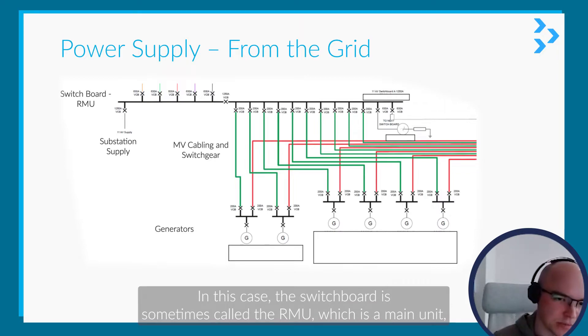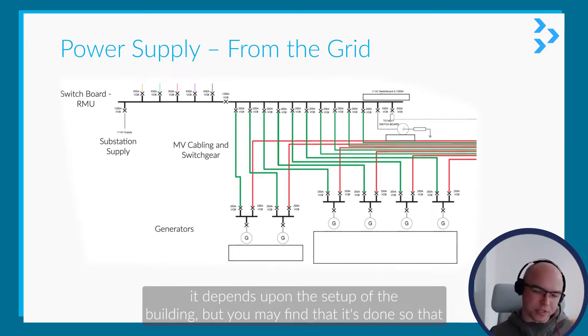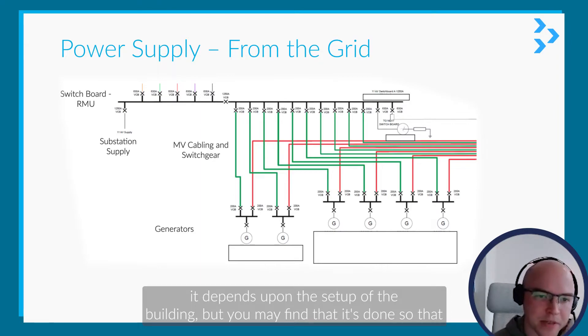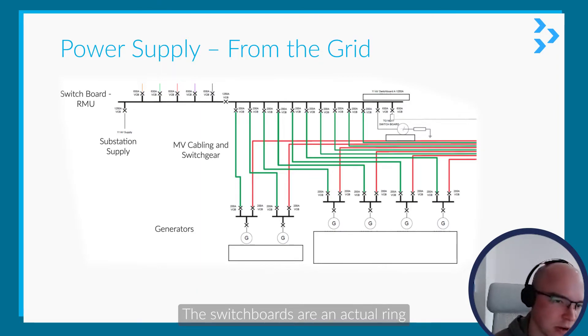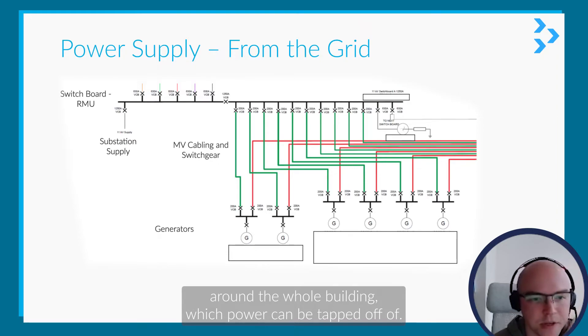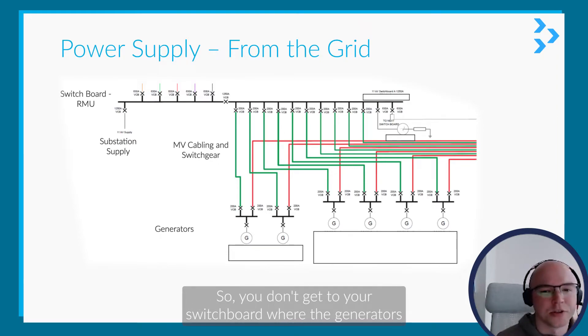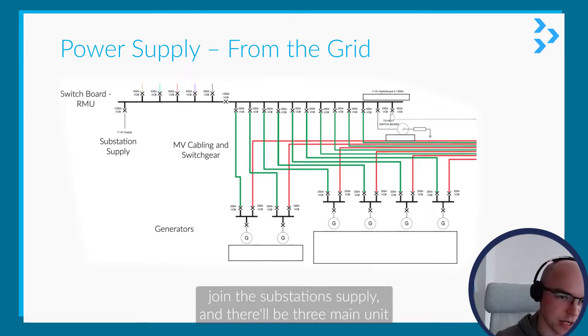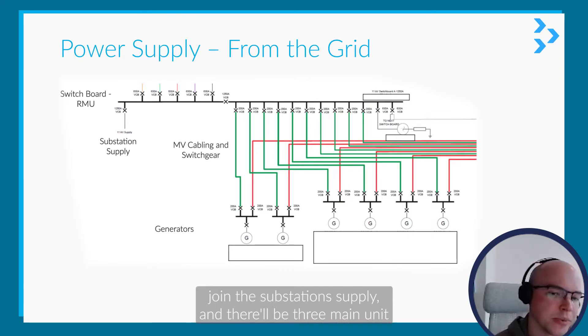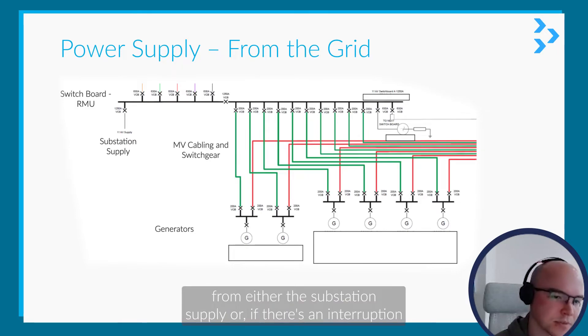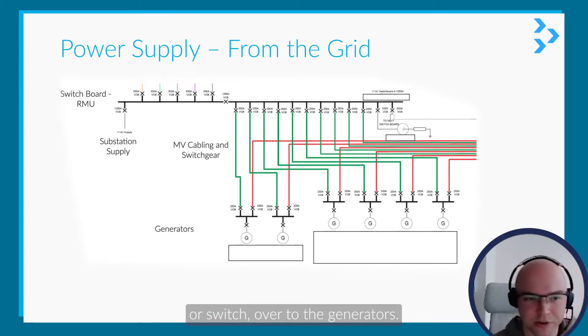The switchboard is sometimes called the RMU, which is a ring main unit. Depending on the setup of the building, it may be done in switchboards or as an actual ring around the whole building that power can be tapped off of. You then get to your switchboard where the generators join the substation supply, and the ring main unit can switch over from the substation supply or, if there's an interruption, switch over to the generators.